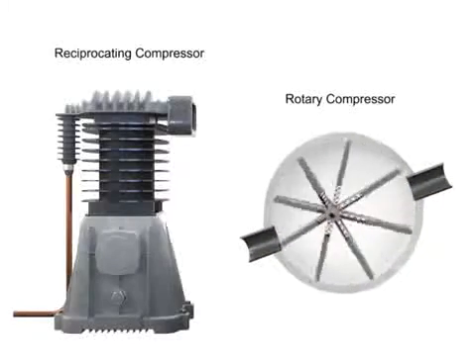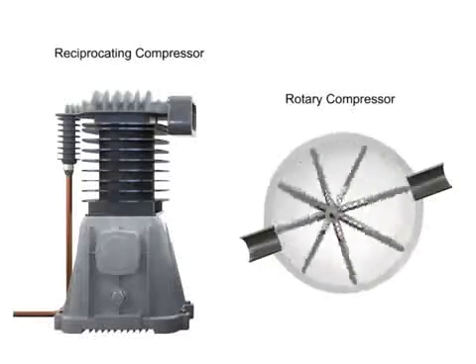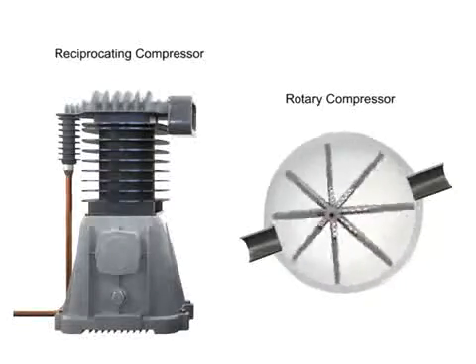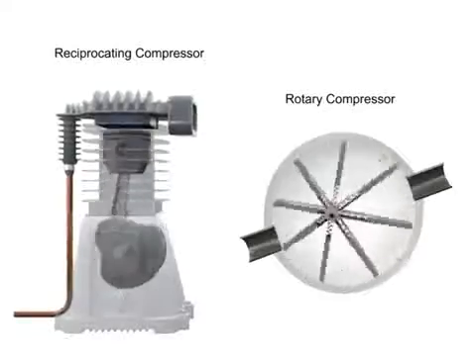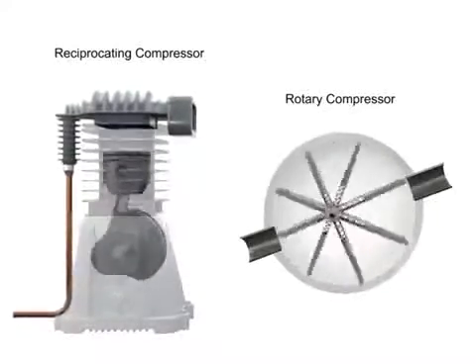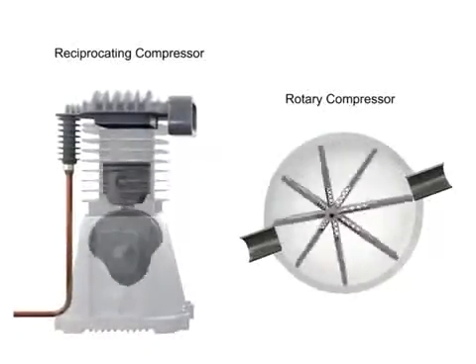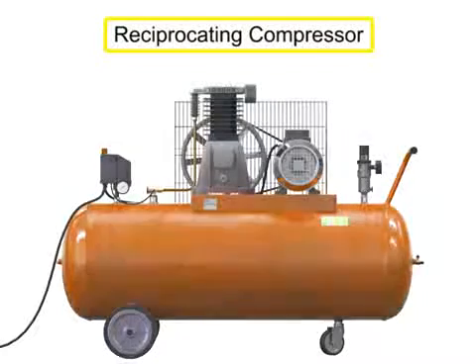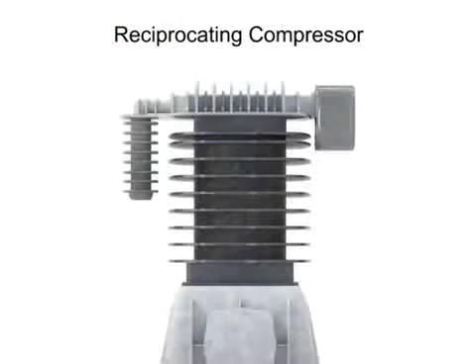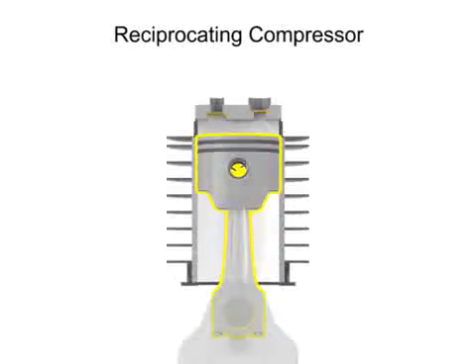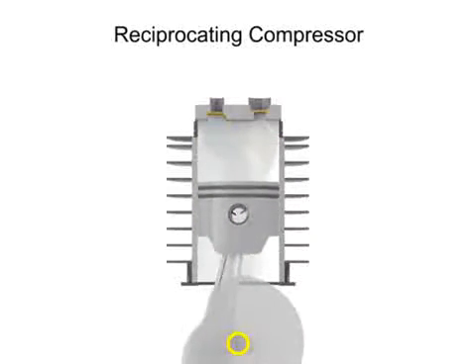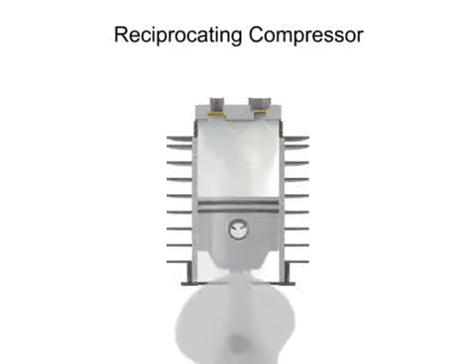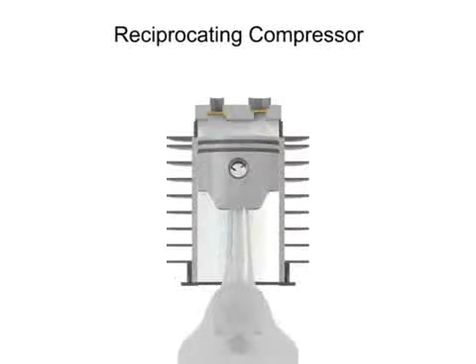Rotary compressors are typically free of the vibration and pulsation that occurs with reciprocating compressors. A typical reciprocating compressor consists of a housing with an internal piston connected to a crankshaft. As the crankshaft turns, a piston reciprocates within the cylindrical housing. There are two valves at the head of the cylinder: an inlet and an outlet.